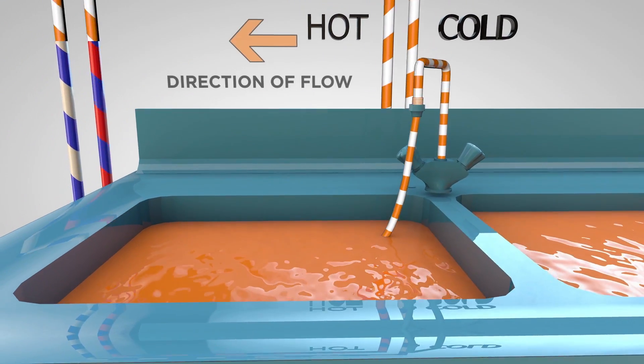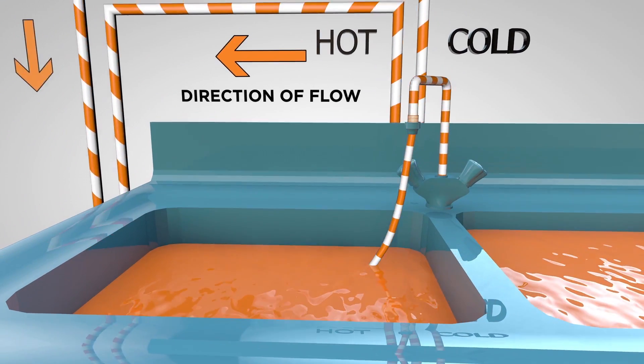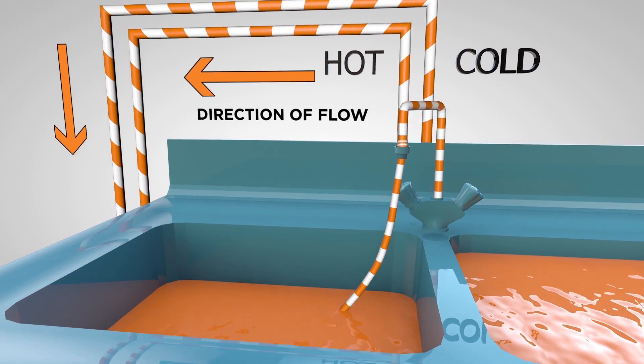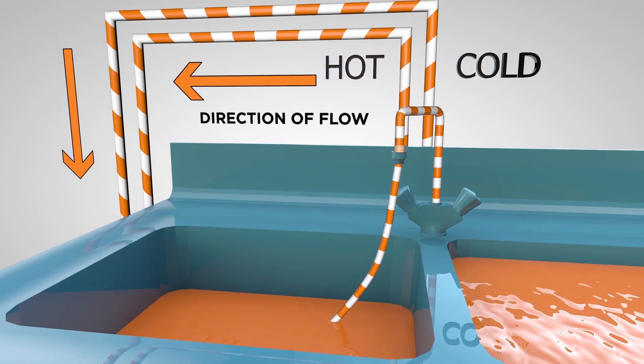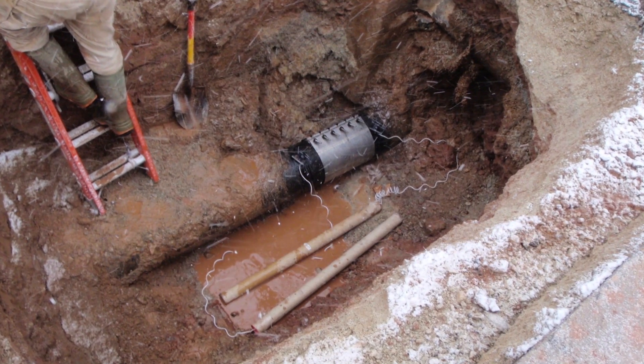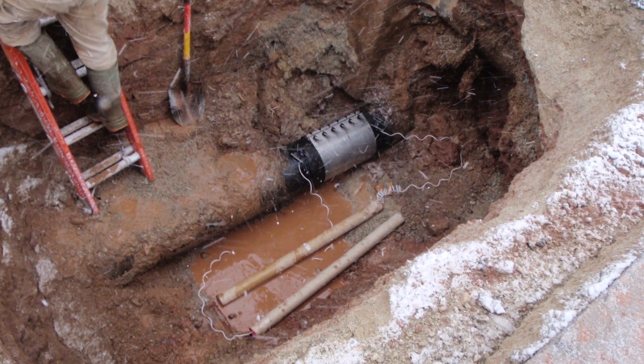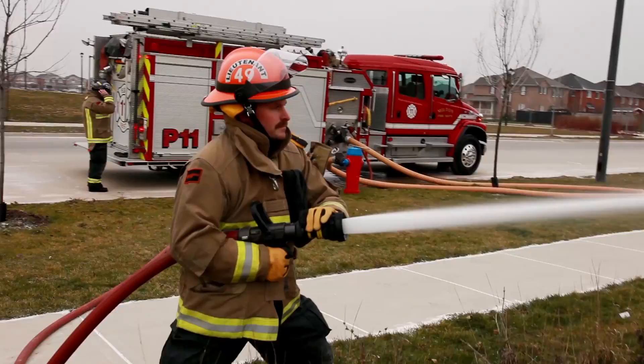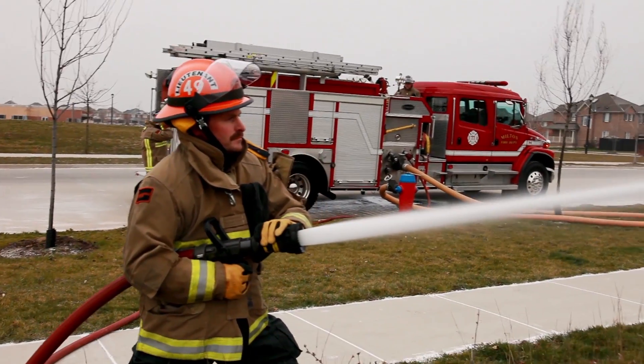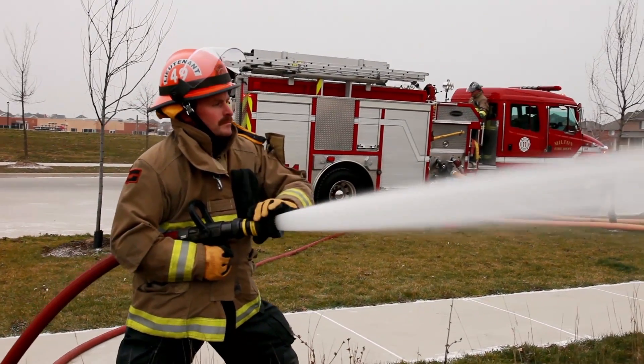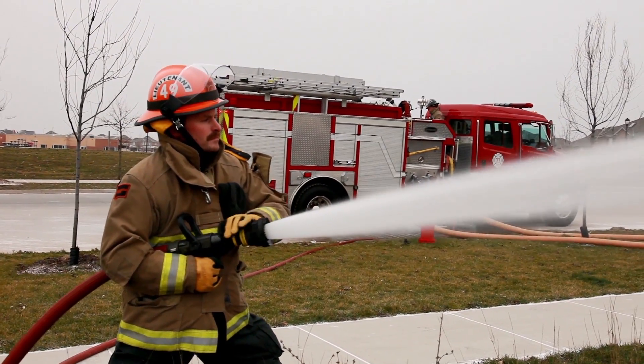Backflow from back siphonage is caused by a negative pressure, such as a drop in the water main pressure. Events that can cause back siphonage include a water main break, power outage, or a high rate of water removal from the system, such as firefighting.